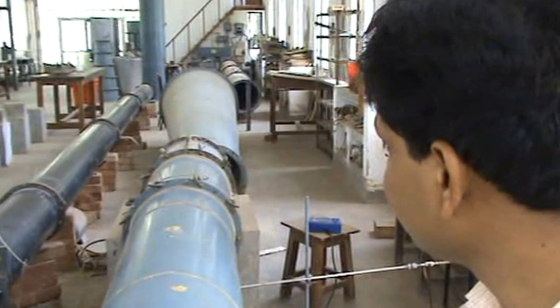We will select a tower section here, and this tower section is selected a bit of distance before the fan, so that as far as possible a fully developed flow situation is maintained. And we will measure the static pressure here, and at the inlet of the fan we will measure the velocity pressure, and whatever velocity pressure we observe over here will be the velocity pressure across this duct, since it's a uniform duct. And from this velocity measurement, if you multiply by the area of the cross section, we can get the quantity flow.